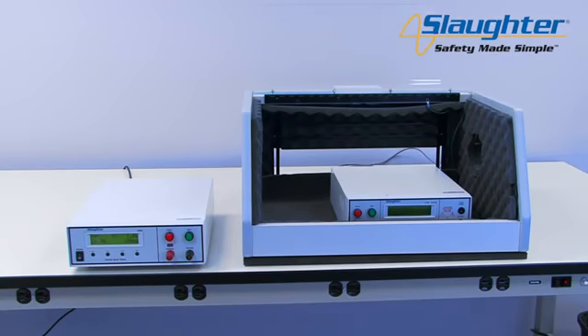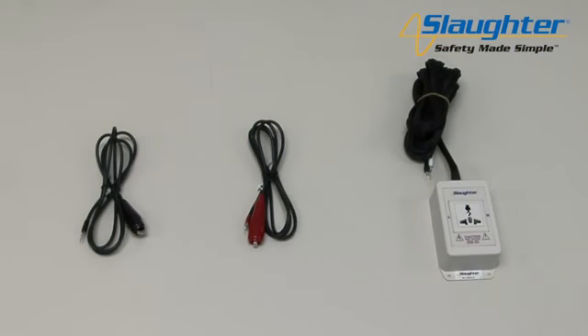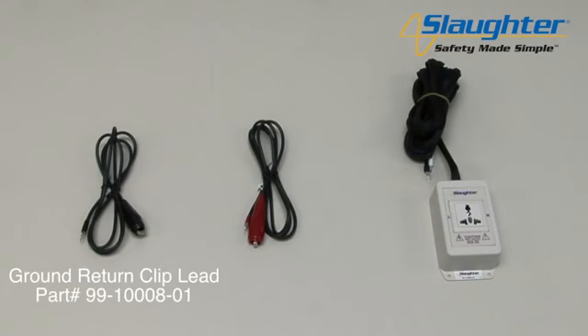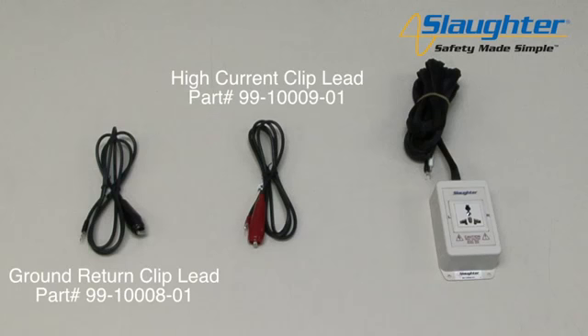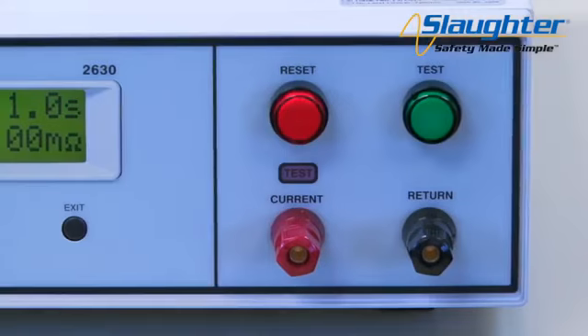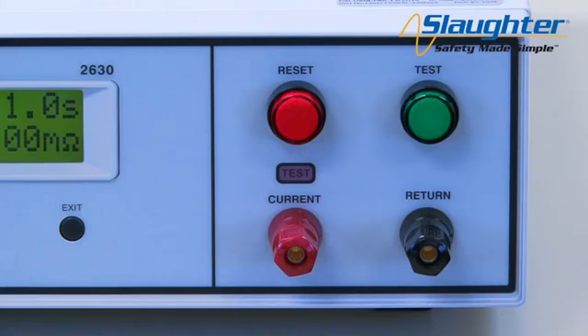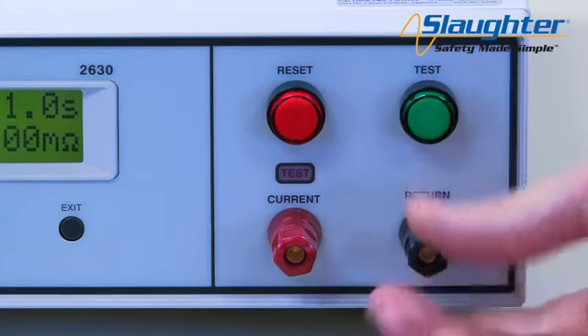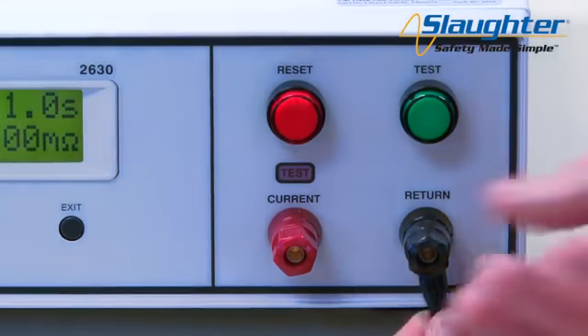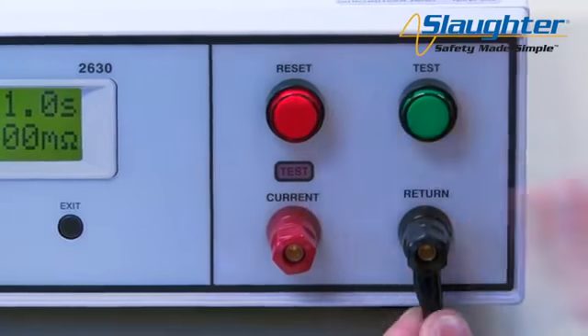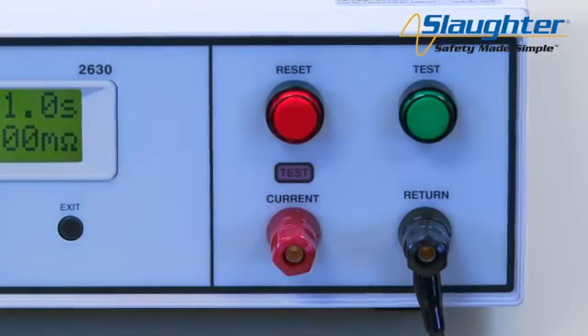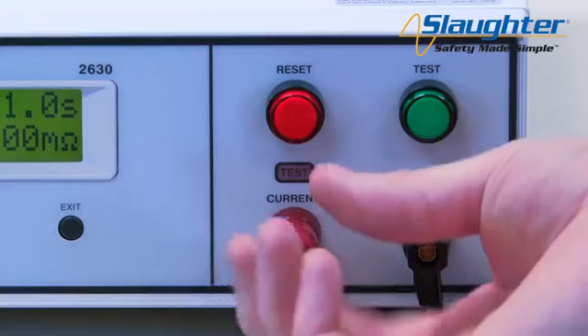Finally, we're going to show you how to connect the 2630 to a DUT and run the test sequence we have set up. To connect the 2630 to the DUT, you're going to need the following accessories: the ground return clip lead, the high current clip lead. If using the optional universal style adapter box instead of the clip style leads, you will need the adapter box. First, connect the return lead to the return terminal of the 2630 tester. Unscrew the return terminal and place the return lead lug over the exposed conductor on the return terminal. Screw the return terminal back in to tighten the connection. Next, connect the red high current lead in the same fashion as the return lead.